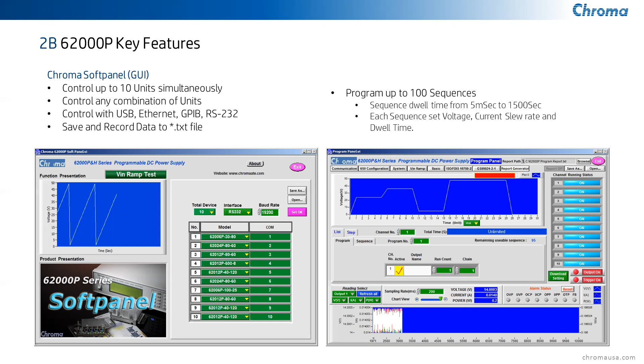Again, 10 units at a time can be controlled, and you can share this program with multiple units. It's used a lot in industry for doing any type of variation and transient inputs to verify devices, whether it's a voltage regulated module, a DC to DC converter, or even DC motors. We can also test just about any kind of electronic device, from cell phones up to higher power conversion units that require a DC input.